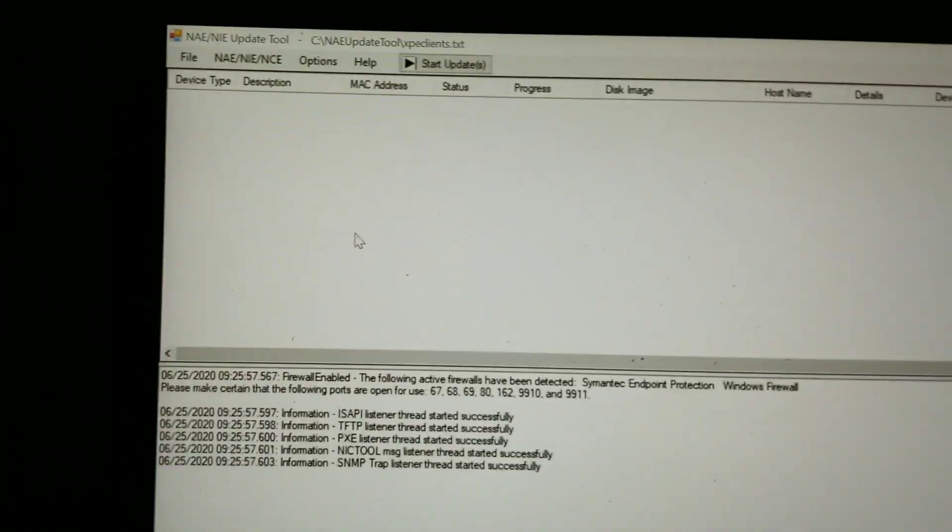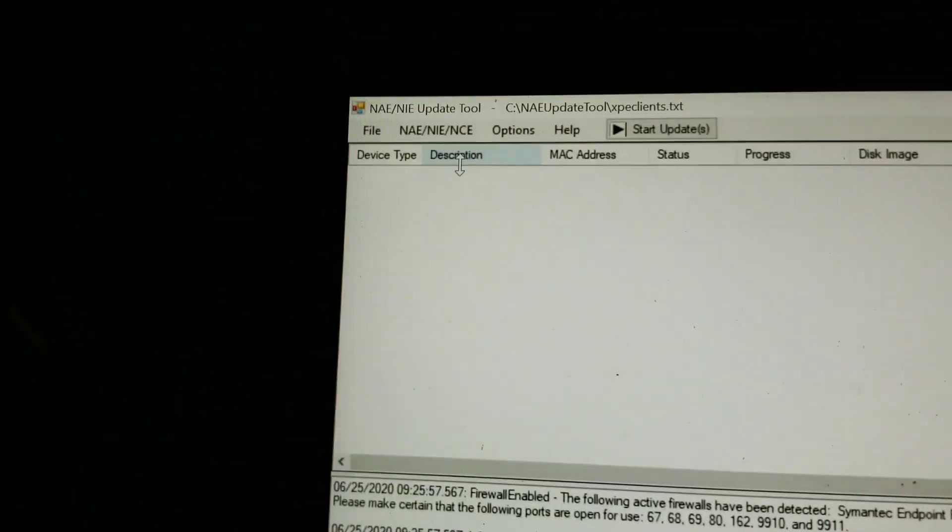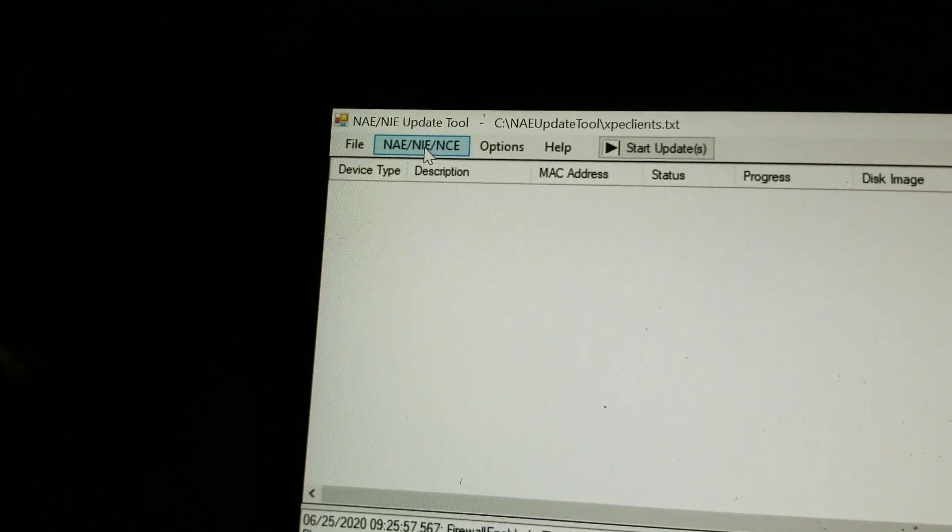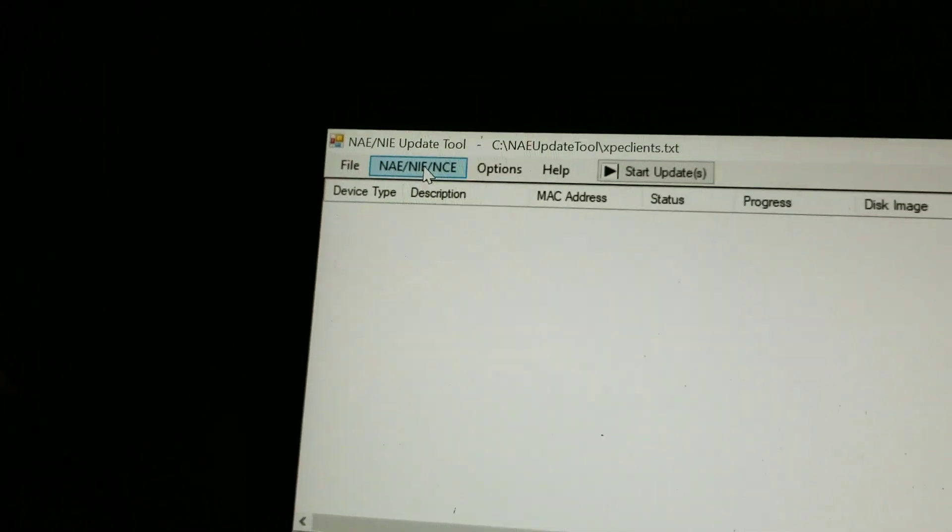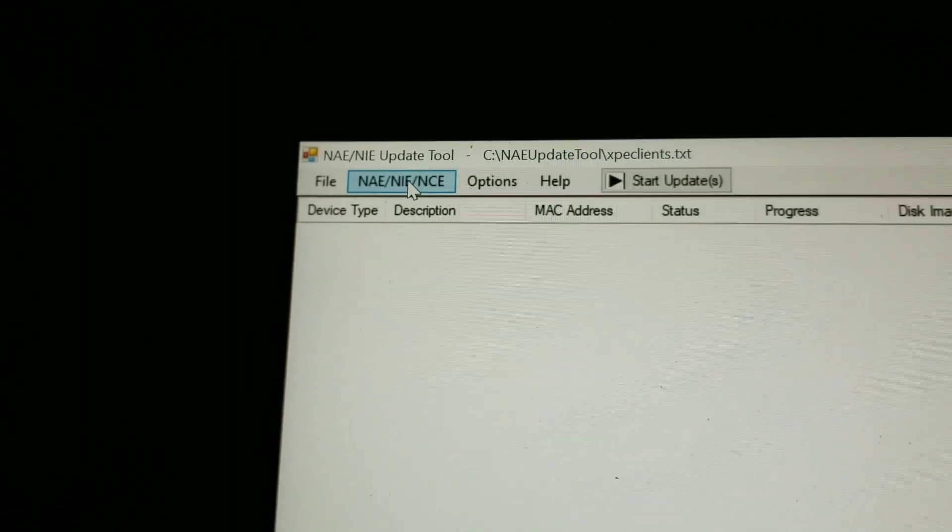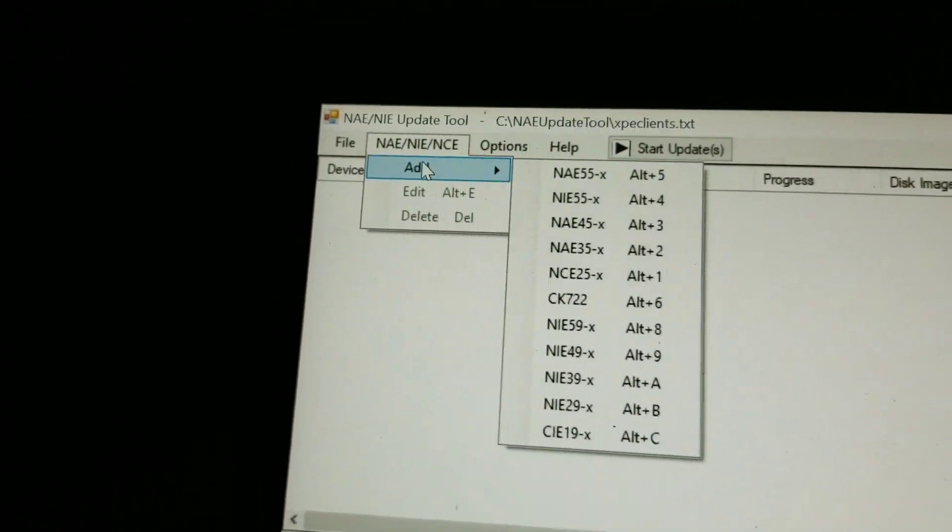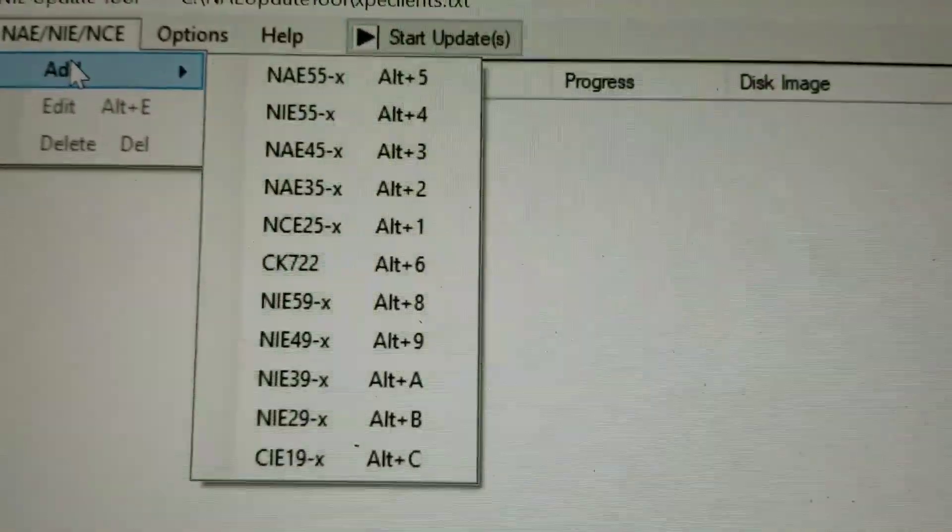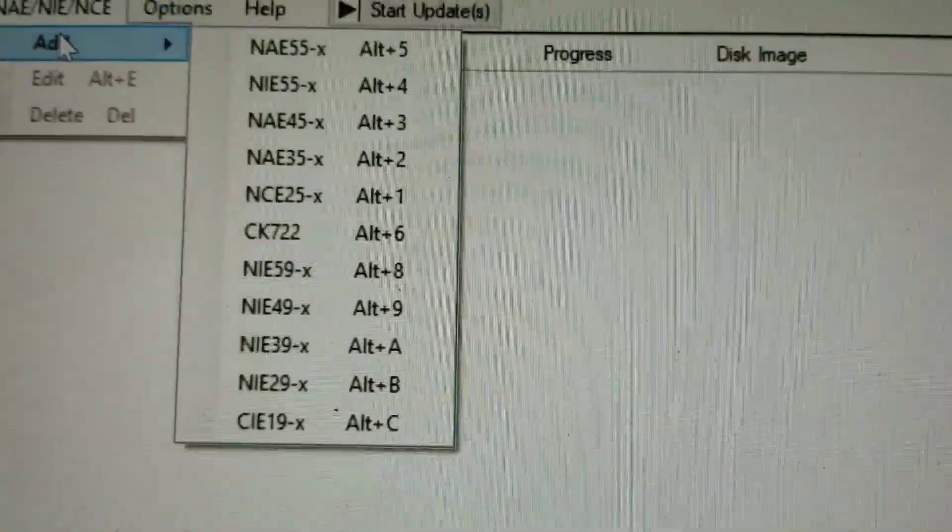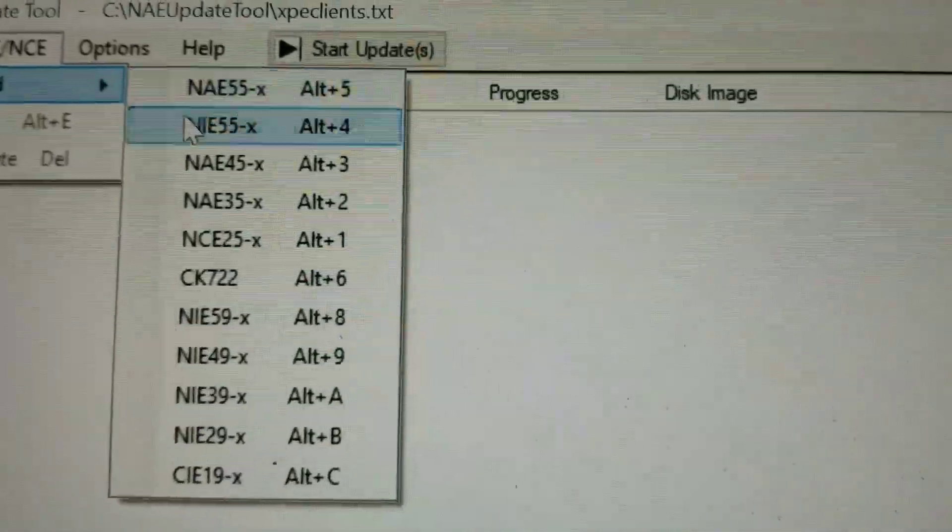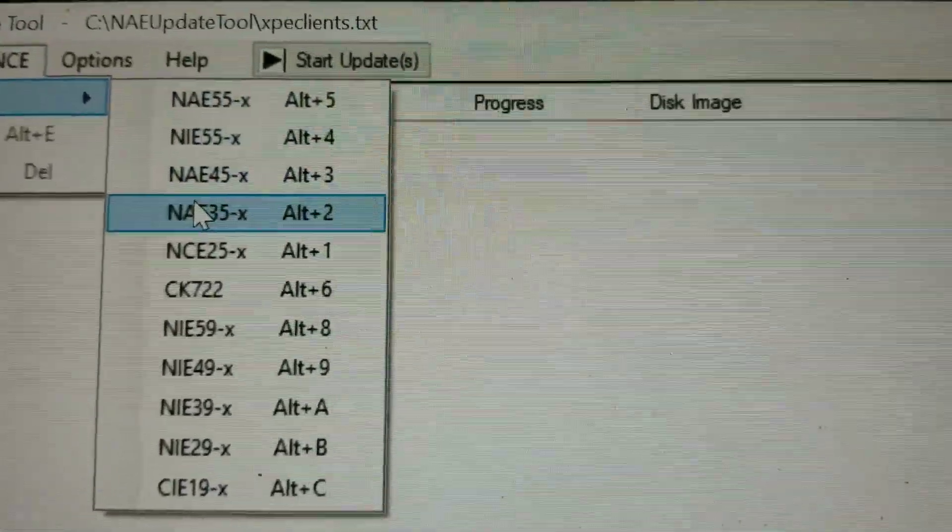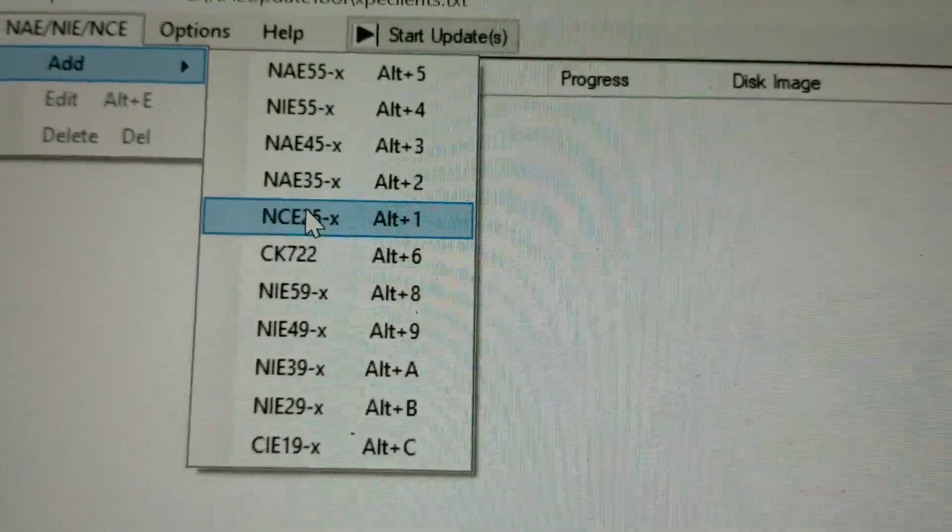Now, the first thing that we need to do from here is go up to the NAE, NIE, NCE button here. Click it. I'm going to select Add. It's going to give me a list of each of the individual devices here. And what I need to do is to go over and select NCE25, which is what this device is.